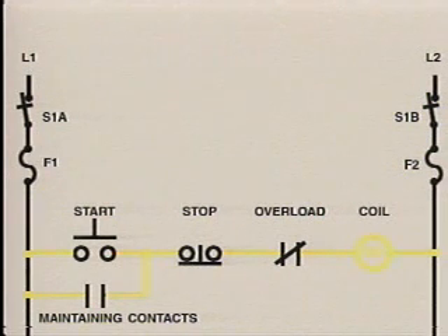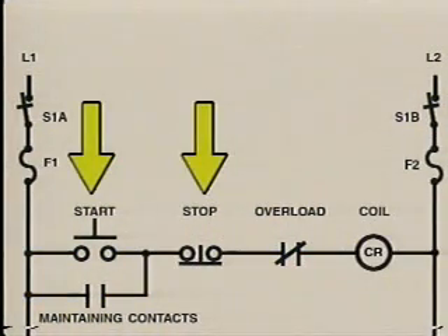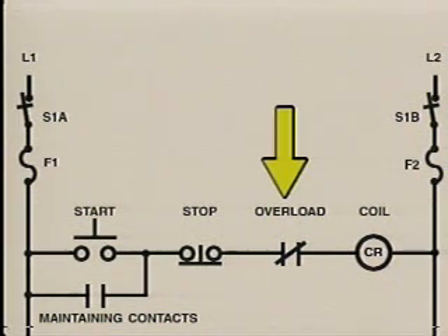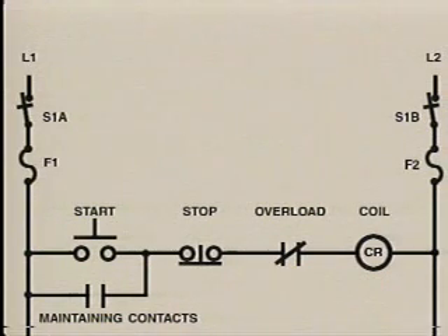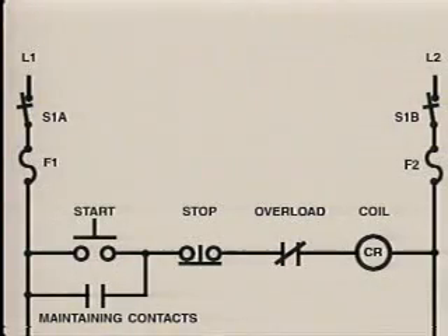However, he does keep in mind that it's easy for wiring to become loose at connection points. That's because of the vibration that's common in most facilities. In this shop, though, there isn't as much vibration as there is in other locations in the plant. The electrician decides that either of the two push-button switches is more likely to have failed than the overload contacts. That's because the push-button switches get used more than the overload contacts. In addition, the overload contacts at least appeared to be in good condition earlier. The electrician does not have as much information regarding the push-button switches.